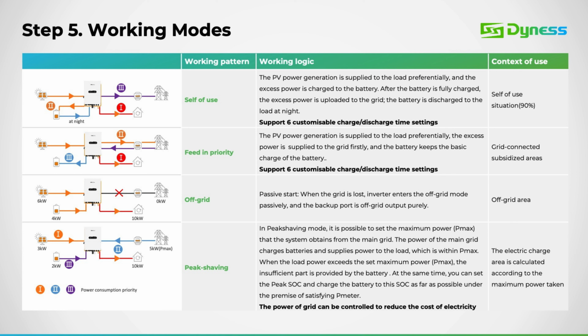Step 5. Working mode configuration. In this final step, you'll configure the working mode to best suit your requirements. We offer 4 working modes. Self-use. This mode prioritizes the load first, battery second, and grid feed-in third. Feed-in priority. Here, the grid feed-in takes precedence, with load being first, feed-in second, and battery charging third. Off-grid mode. This mode prioritizes the load using whatever power source is available, whether it's PV or battery. Peak shaving mode. In this mode, you can set peak shaving on either the grid side or generator side.